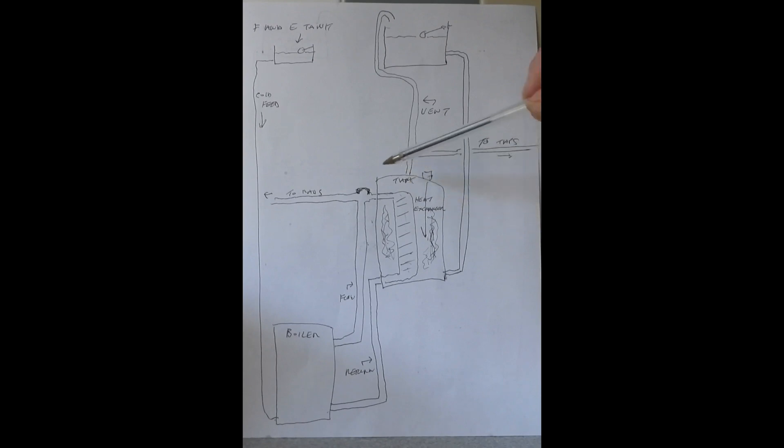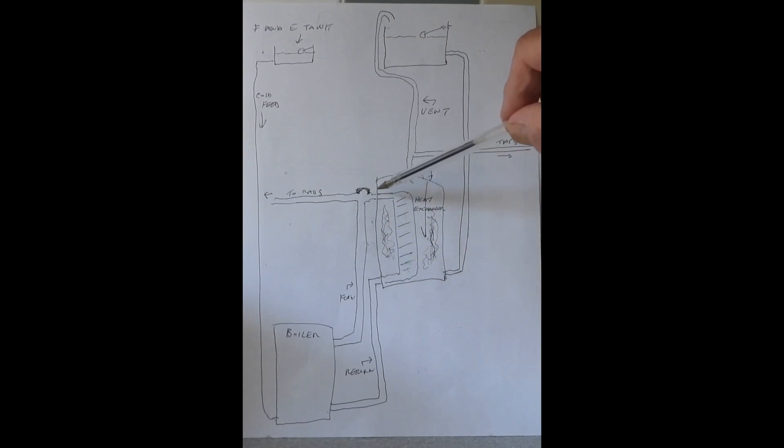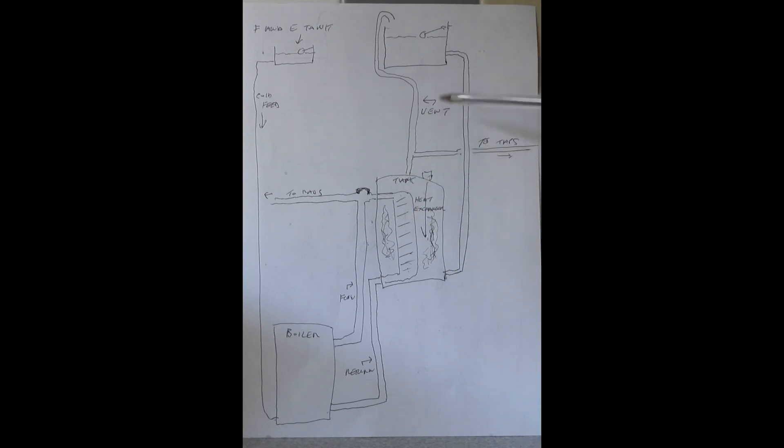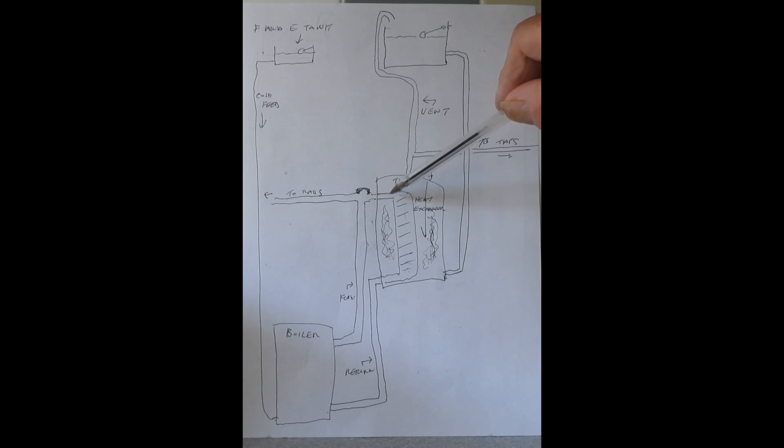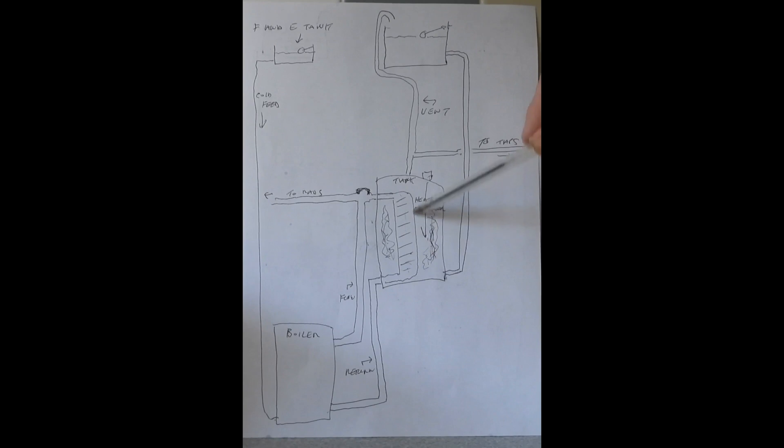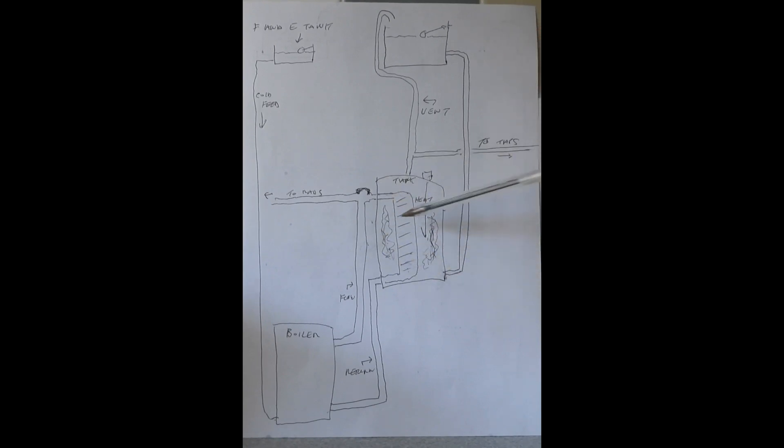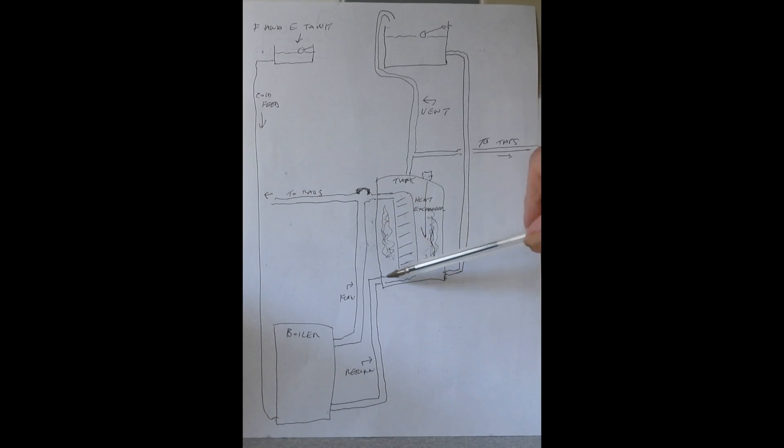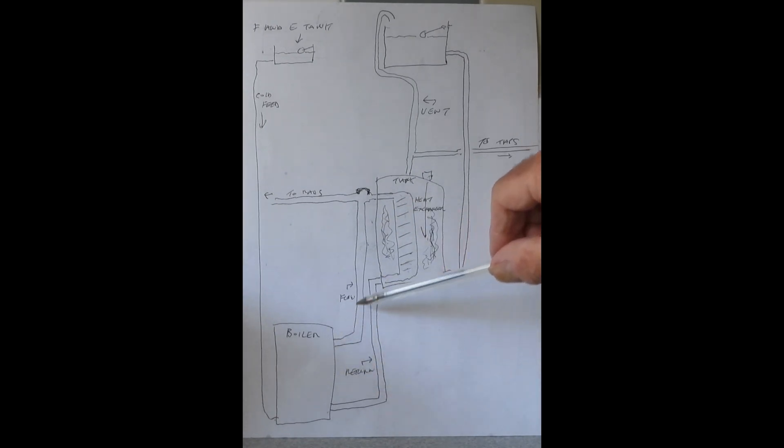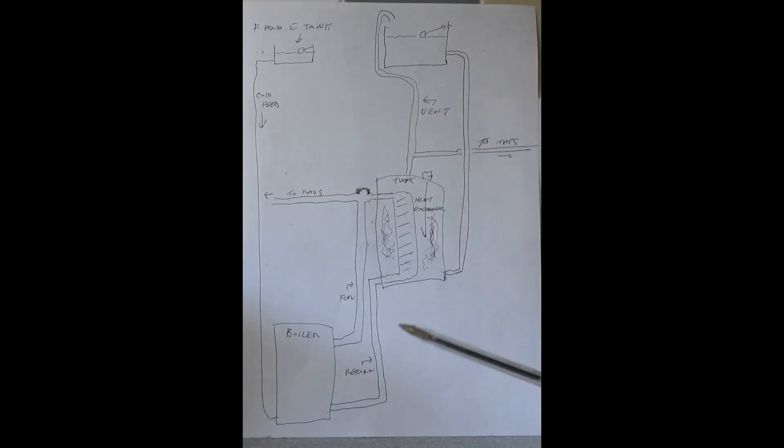Because when those pipes finish at your hot water tank, you just tend to think they just go into the tank and there's just the water, but there isn't. The pipes carry on through the tank into the middle and through this heat exchanger, which is completely sealed. So basically, this water that's in your copper tank doesn't mix with the water that goes around your boiler and heating system. It all stays separate.